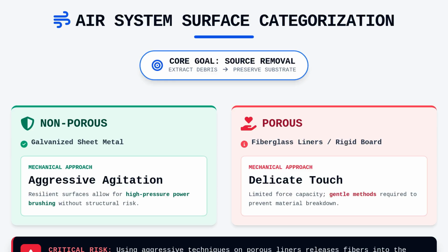The core principle here is that we are performing source removal, which means our objective is to extract debris while leaving the substrate intact. If we apply the same high-pressure power brushing techniques used on sheet metal to a friable fiberglass liner, we risk releasing fibers into the airstream, which is the exact opposite of our intended goal. Understanding this material distinction is the difference between a successful remediation project and one that causes secondary contamination.